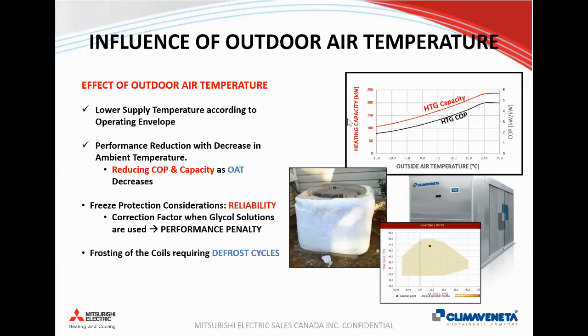The reason we use glycol is mainly for freeze protection and peace of mind. But it's also important to recognize that whenever your heating system operates in the winter, you'll get that system up to the operating temperature, but then it's going to stay at the supply and return temperatures throughout the winter. We're really just concerned about what happens if there's a power loss. So having pumps on emergency circuits and heat tracing on emergency circuits is one strategy to get around that and have a little bit of a boost in the overall efficiency.